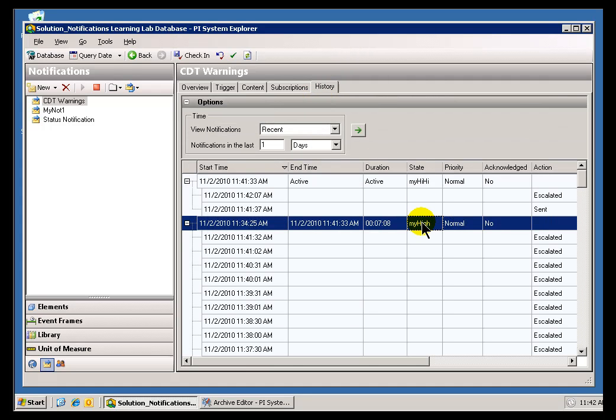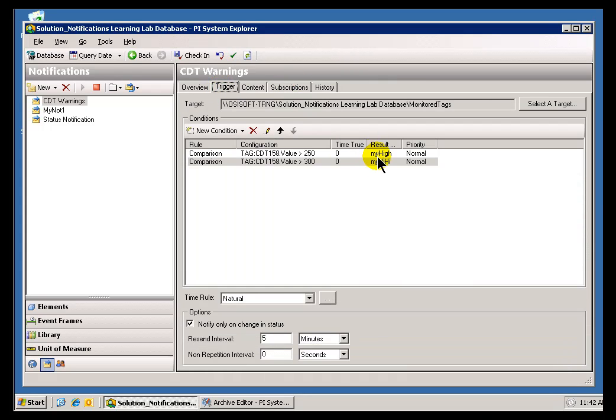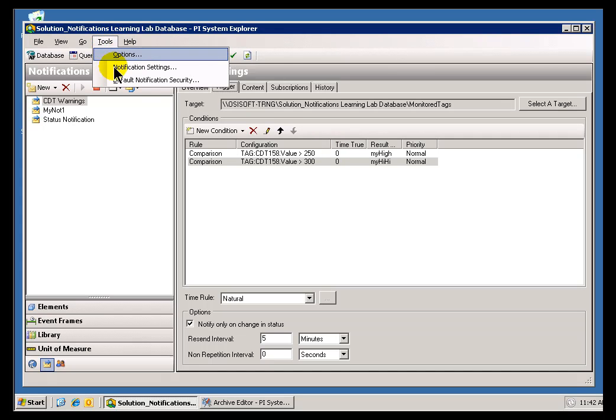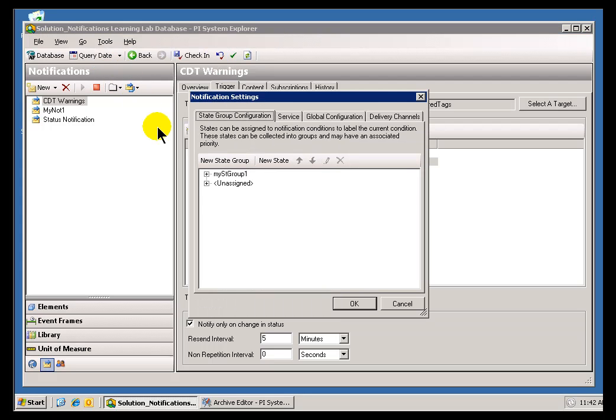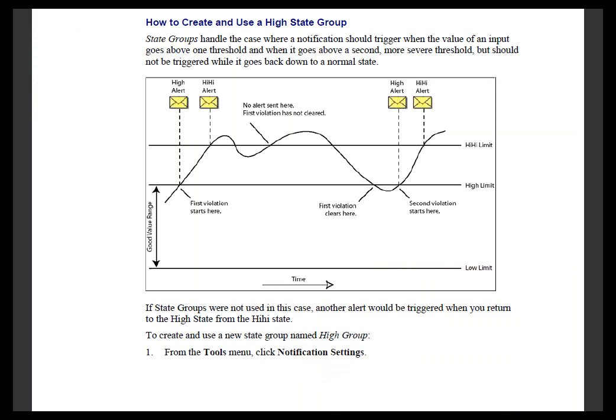They actually will show up in the History of a Notification. So it's something that's going to be useful to show to people — it'll show up in their History and in their Notifications. What we've done to create these is gone into Tools, Notification Settings, and I created what we're calling a State Group. This State Group is where we define the Names of the States and also the Priorities, or Precedents. The order of these does have some ramifications as to when things go into Alarm and when they come out of Alarm.